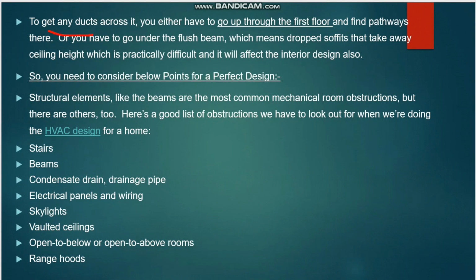So to get any duct across, either you have to go up through the first floor and find a pathway, and in this case we have a room here, so we have to create a shaft here. From the AHU unit, the supply and return duct will both go through the shaft and from there go above the first floor. From the first floor it goes down again, back to the ground floor, and from the ground floor the duct will pass. So we will have this type of complicated, very extended, lengthy design for this ground floor if you don't judge the room in the initial stage.